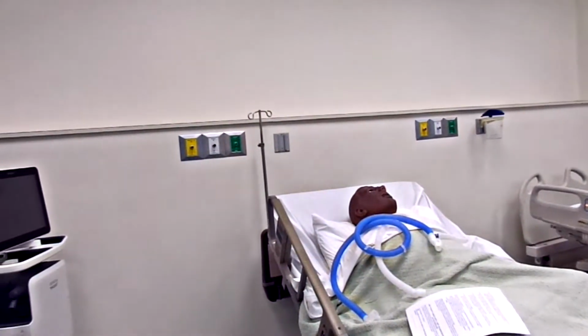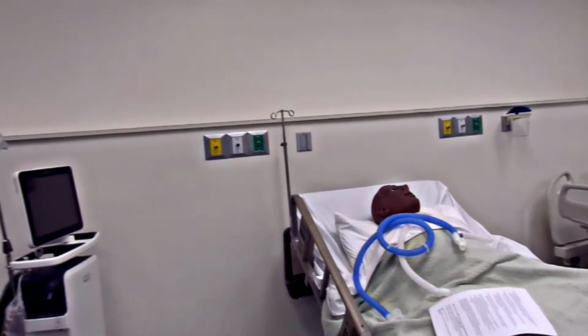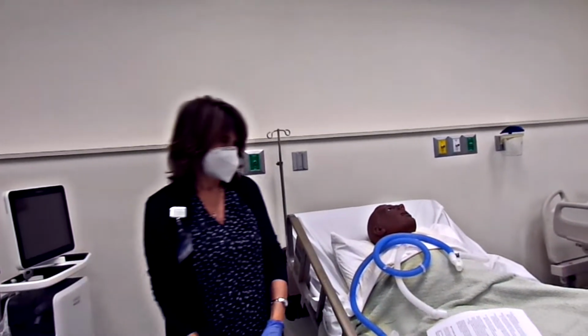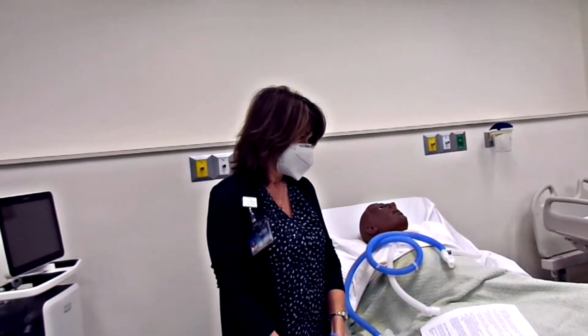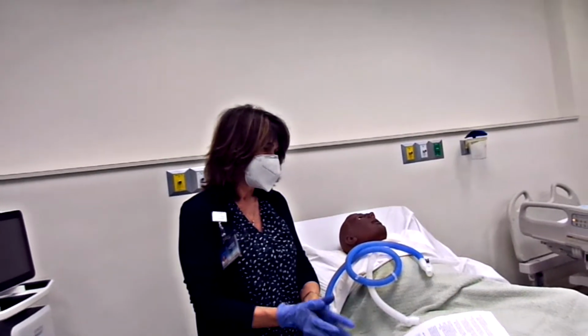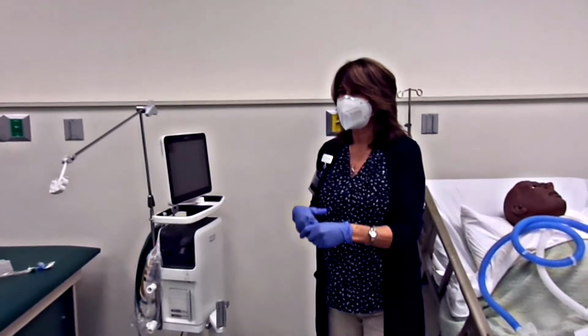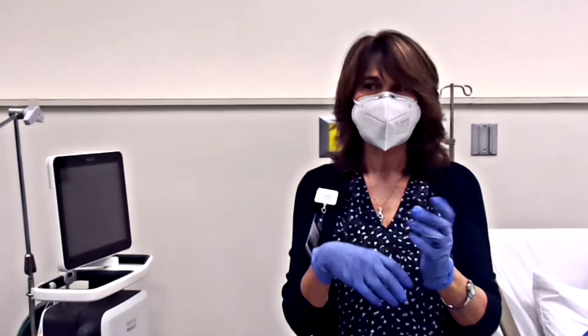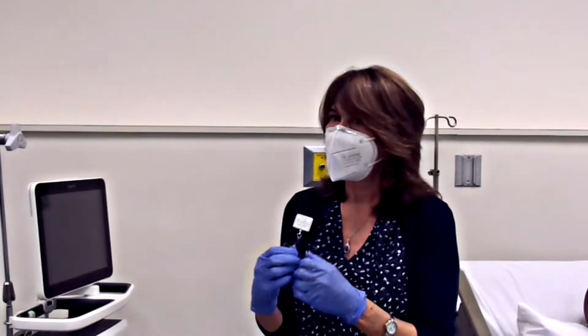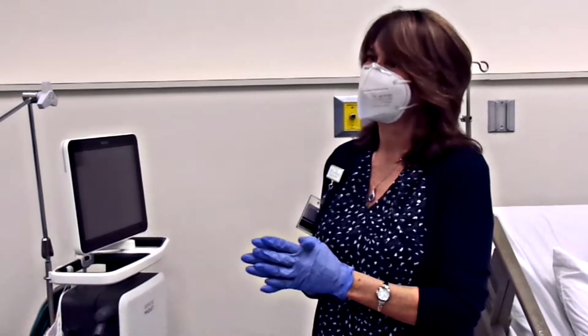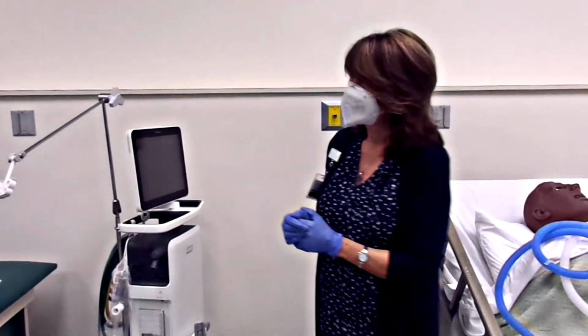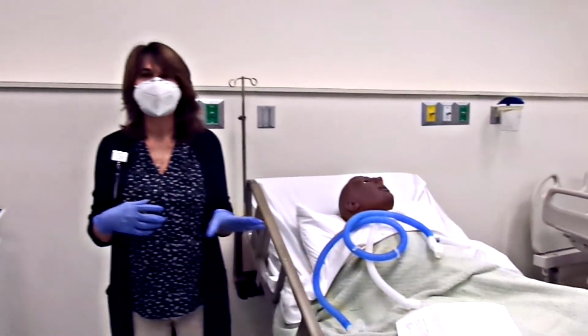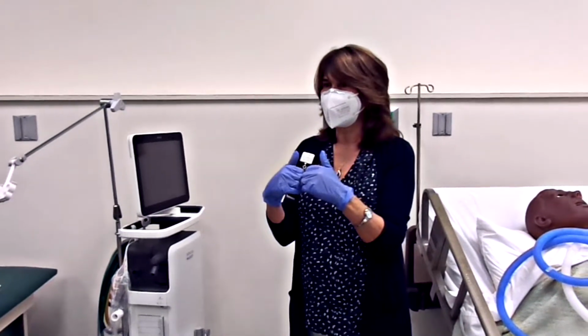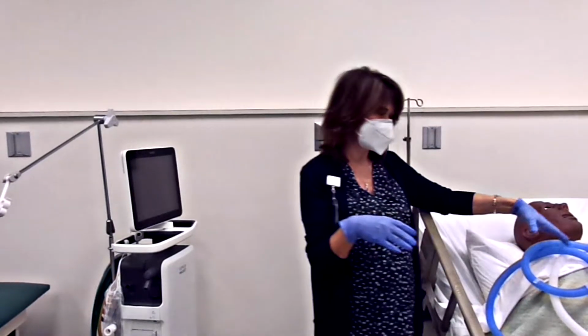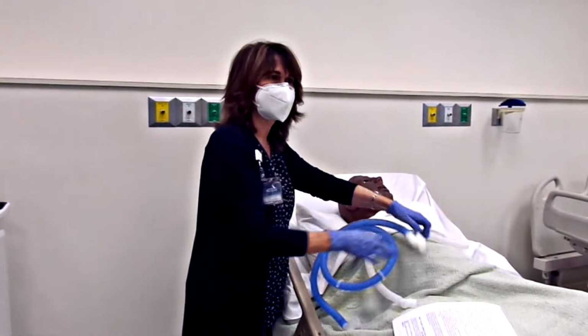Explain why it is necessary to have no leaks in the circuit. Instead of the air entering the patient's lungs, the air will exit through the leak in the circuit. This will cause less air delivery to the patient's lungs. When you put the circuit under pressure to deliver the positive pressure breath, if there's any openings or if you don't have a tight connection, air will go out there instead of going into the patient's lungs. So you lose volume and pressure? Yes, very good. I remember that. Good job. Yeah, so that's one thing that you're always checking: if you notice that your VTI and your VTE are different and you're missing volume, you check your circuit, make sure everything is tight, push and twist to make sure it's tight.